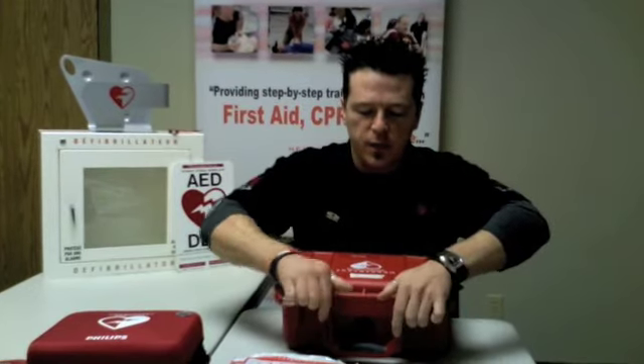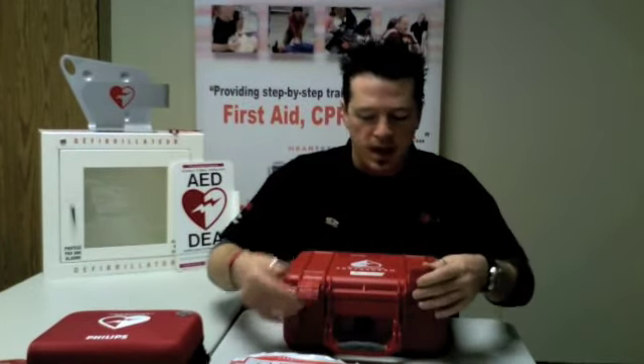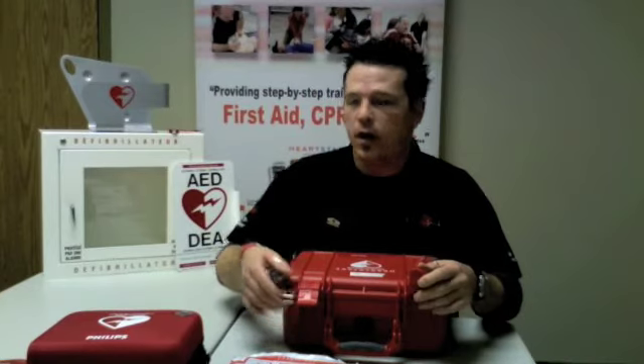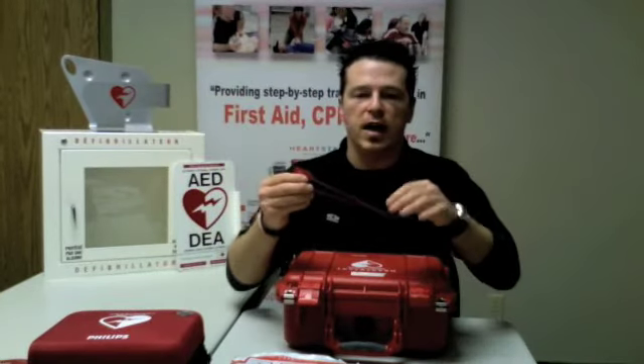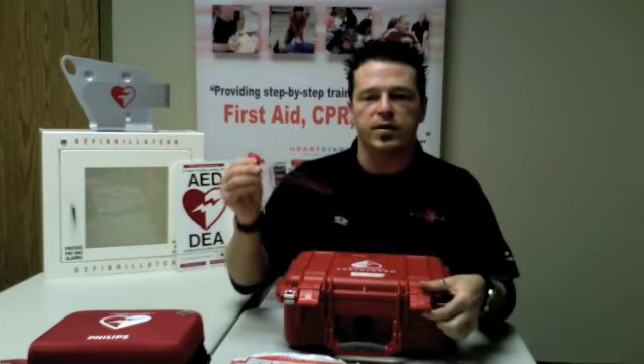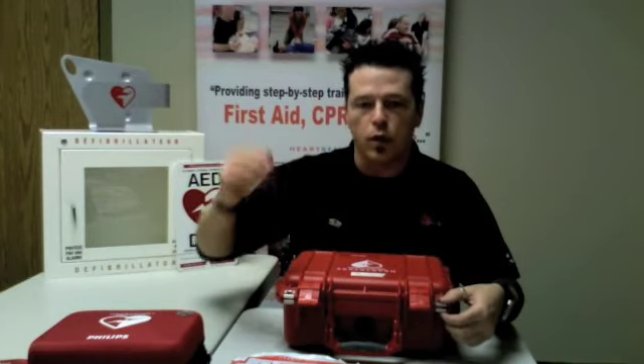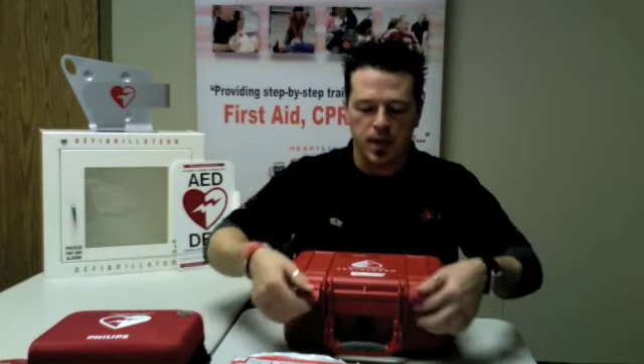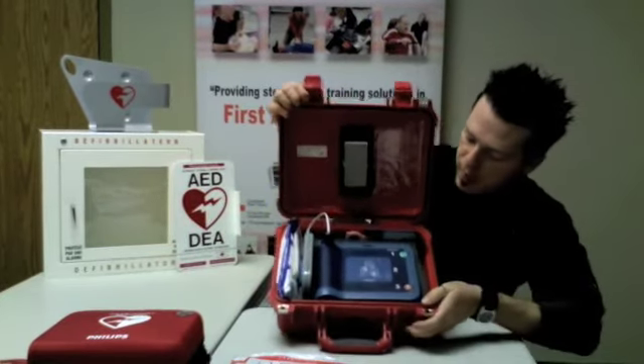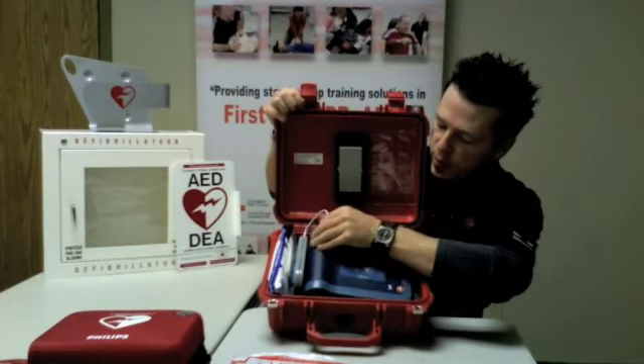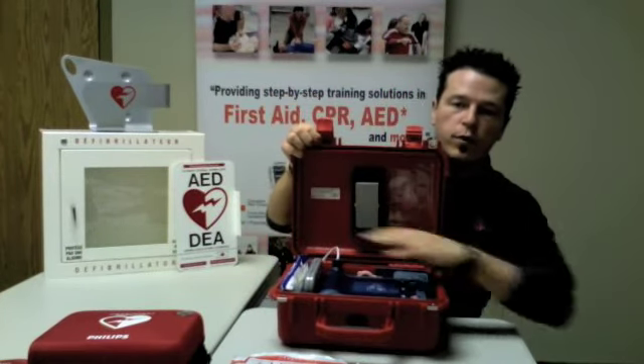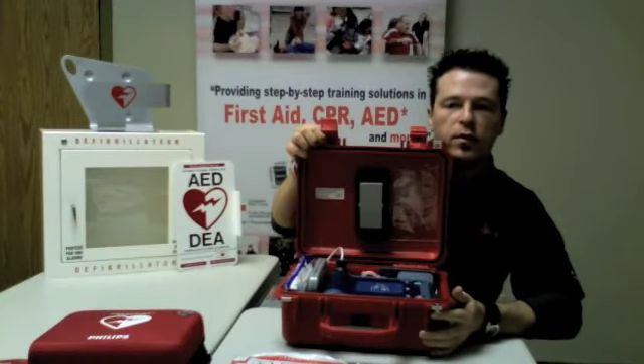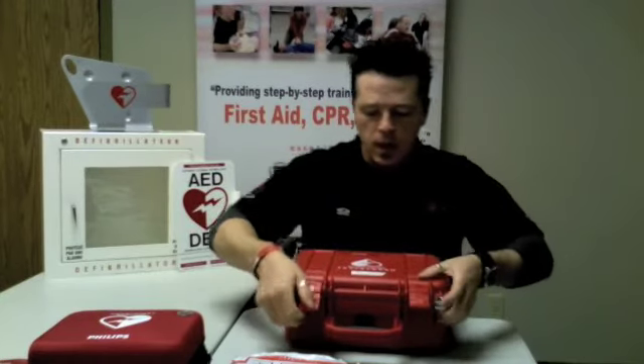And to access the defibrillator would be to just take up these 2 clips. If there's a lock on it, then it would obviously to take off the lock. It is possible also that there are these little tie wraps that are being used to make sure that the defibrillator itself has not been tampered with that go through these little holes. Again, that's a company policy decision. Accessing the defibrillator, you would be able to see that it would be as simple as taking out the defibrillator from the case itself and to go through making sure that all the accessories that are related to the defibrillator are in place. So that's the completion of the diagnostic test for the Philips HeartStart on-site as well as home defibrillators.